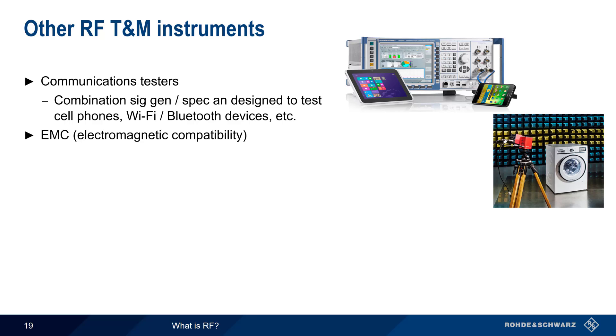In EMC, or electromagnetic compatibility testing, we're interested in two things. First, whether electrically powered devices are unintentionally radiating RF that could interfere with other devices. For example, whether a washing machine interferes with our cell phone reception. Conversely, we might also want to check if devices are adversely affected by RF. In this case, whether our cellular devices or base stations cause washing machines to malfunction.